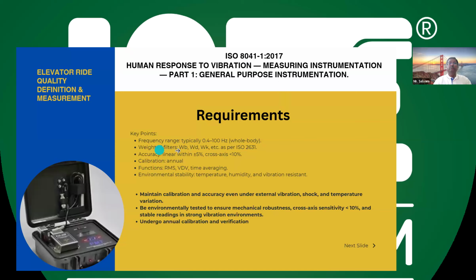For example, key points are that this accelerometer can capture signals from 0.4 to 100 hertz, it can respond and filter. The software will be designed for the whole body, with some filtering mechanism, and accuracy, linear as well as cross axis. Also, we need to calibrate every year. And functions, for example, normally some peak to peak value and average values are used in elevators. In escalators, they use the RMS value, root mean square value, all these things. And it has to be stable temperature-wise and humidity-wise.